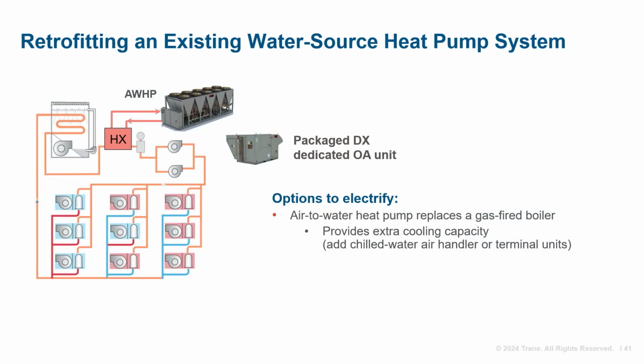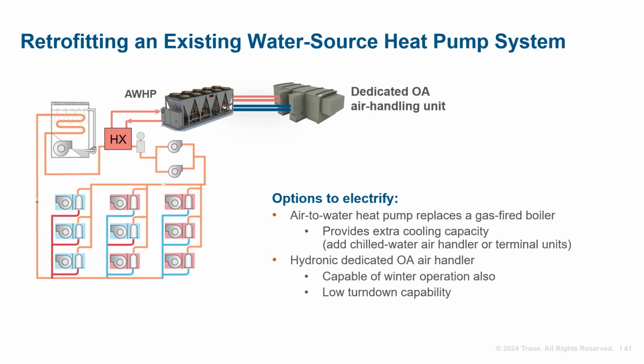If the existing system uses a packaged DX dedicated outdoor air unit, you might add a chilled water air handler or terminal units to utilize this excess cooling capacity. But a DX unit often uses either gas or electric heat, so you would add a new hydronic dedicated outdoor air handler for ventilation. This can be used in the winter months also. The air-to-water heat pump sends hot water to the air handler to warm the outdoor air from 0 degrees to 75 degrees. And a hydronic air handler is very capable of very low turndown of airflow for demand control ventilation. Using an air-to-water heat pump with a hydronic outdoor air handler enables these energy savings that may not be possible with a DX dedicated outdoor air unit.